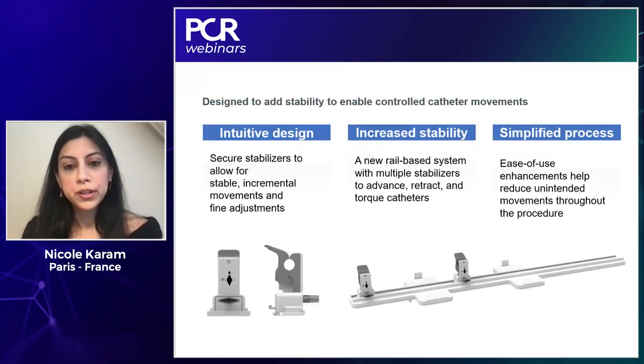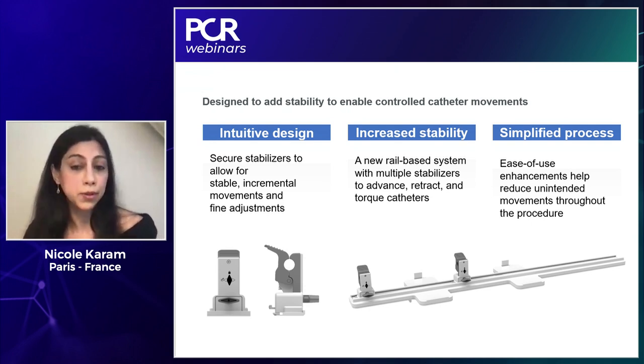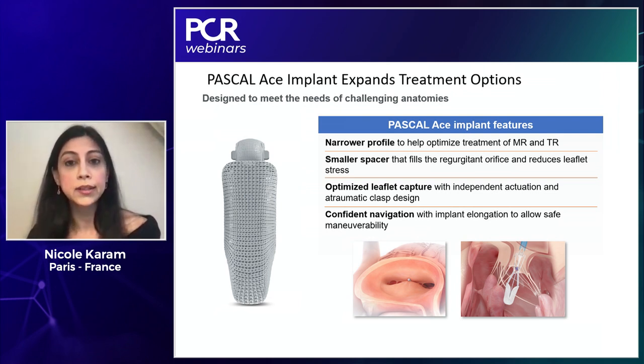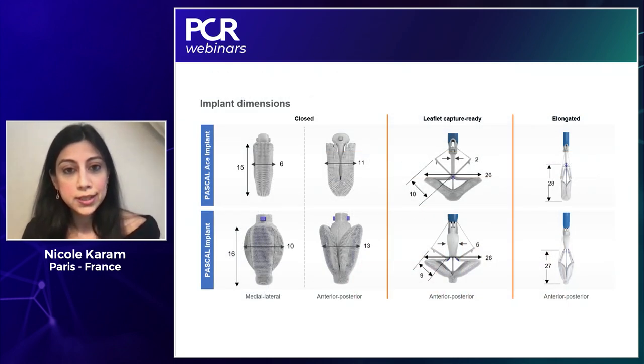What is also new is the change in the device stabilizer. We now have a stabilizer using a rail-based system, with multiple stabilizers that will be implanted on the same rail system. It allows increased stability and is optimal for single operator use. The Pascal ACE has a narrower profile, so it's easier to navigate with. It has a smaller spacer and still has the possibility of separate grasping, which allows us to take one leaflet at a time or to optimize if needed.